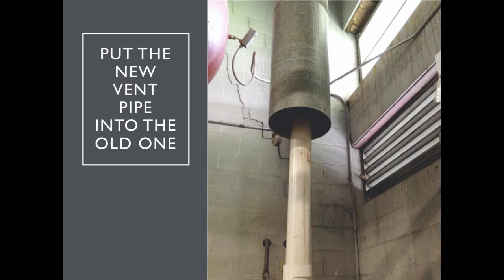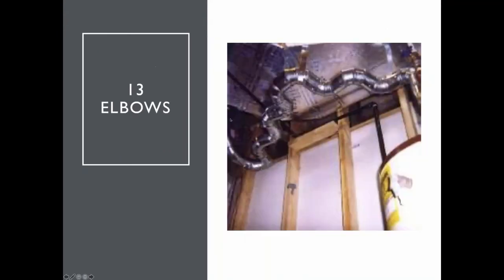I took a picture of this. I wish I had a picture of the vapors coming up. But they had put this in themselves, and this had been in for about 5 years, and no one called them on it. And it's really, really dangerous. The carbon monoxide levels in this boiler room were very high.